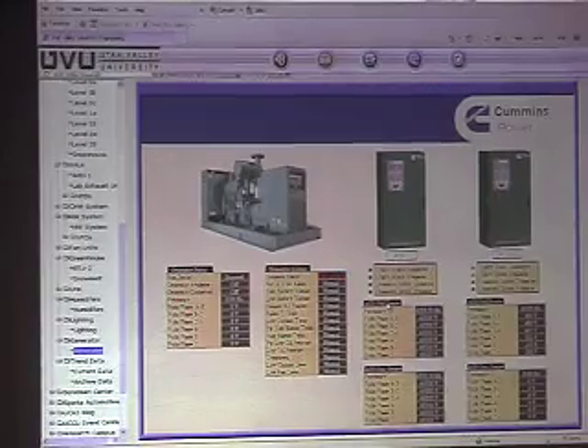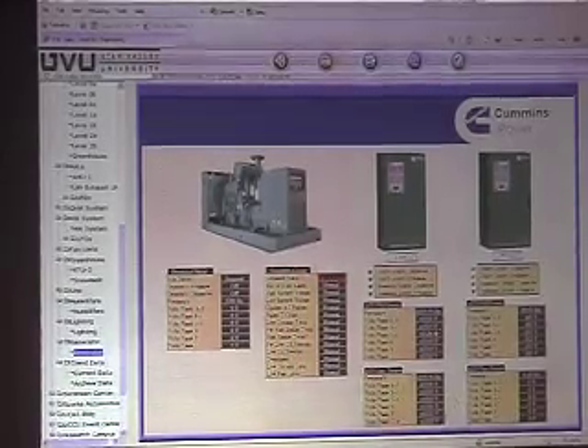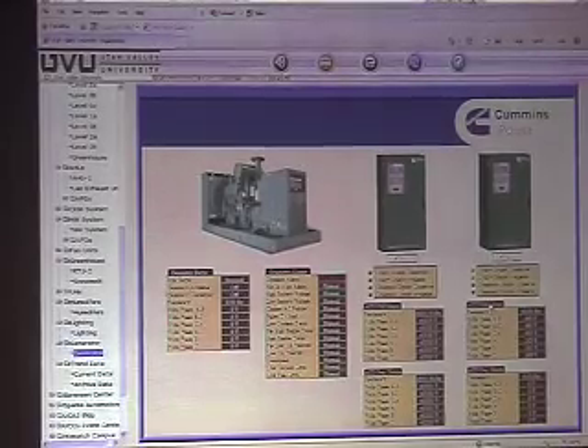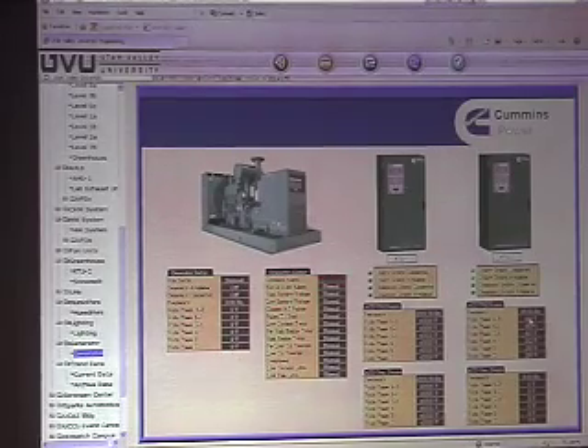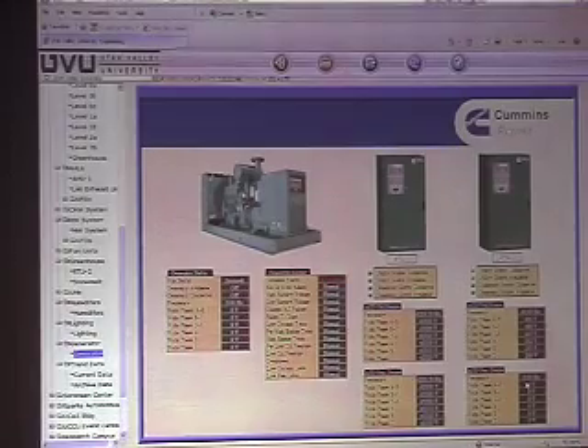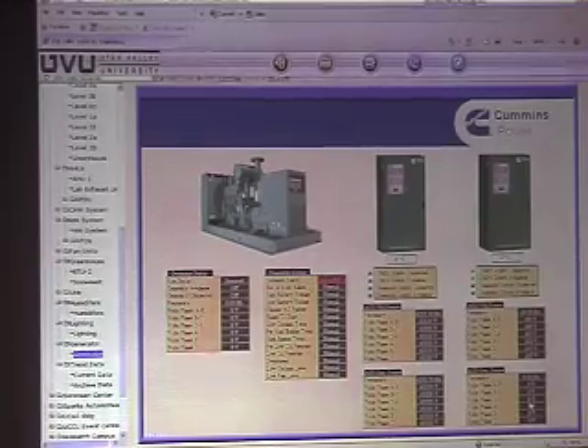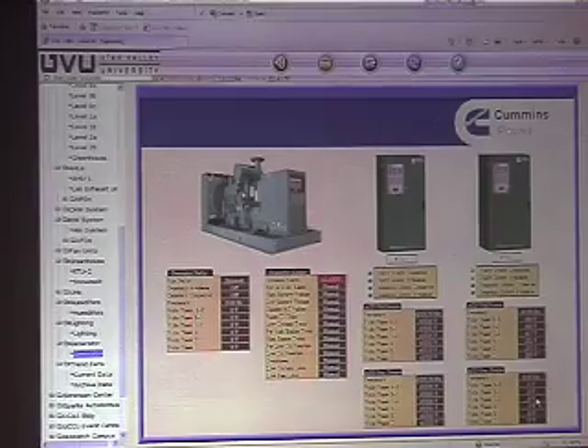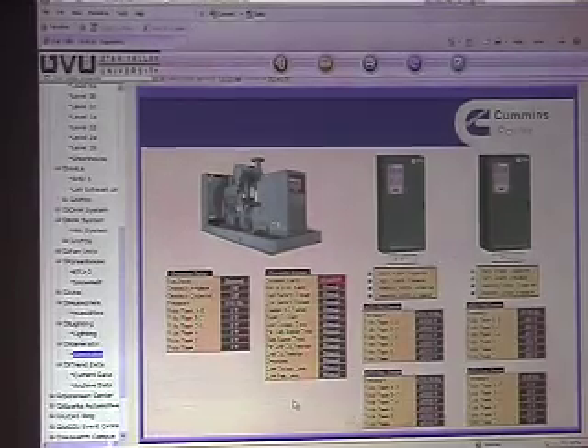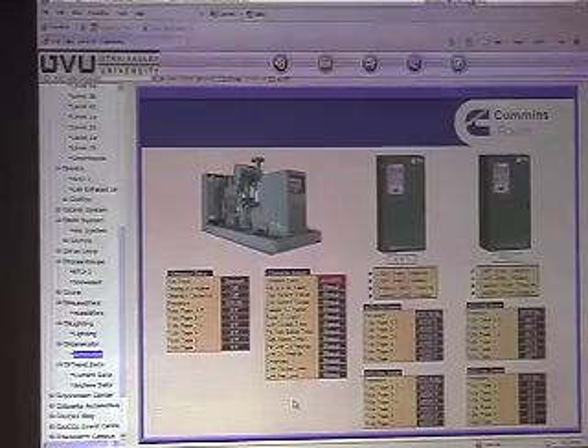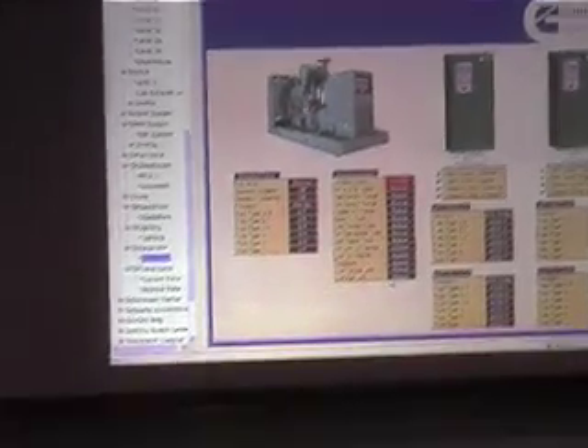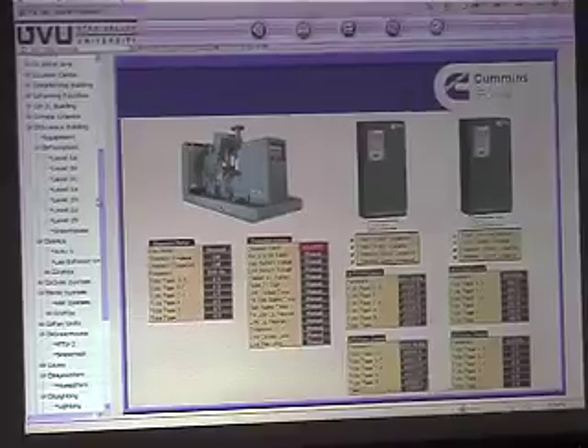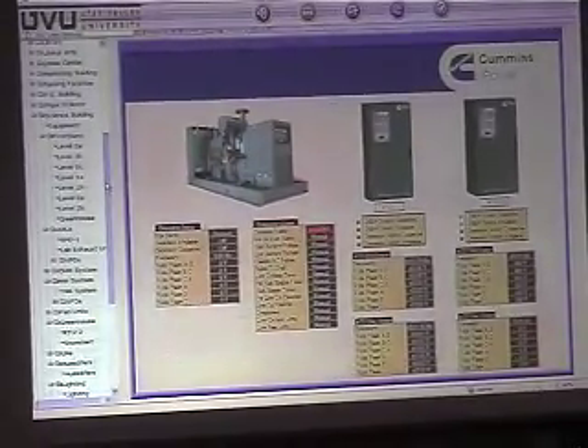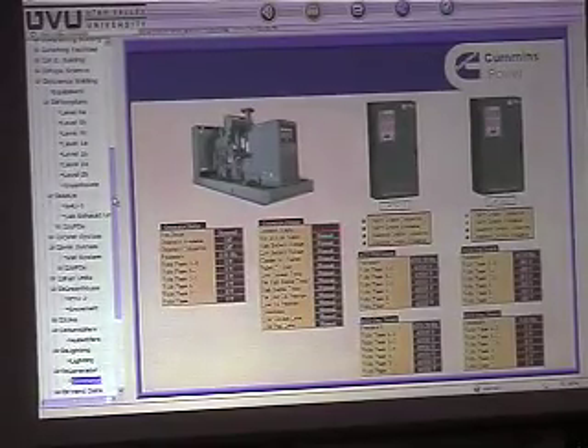And then your volts and frequency on your transfer switches. So you've got the utility source and generator source. When you lose power on your utility side, these will most likely go to 0. And then when your generator kicks on, you'll see voltage on this side here that is being supplied to the transfer switch. Where are the transfer switches located? They're right down here in the electrical vault, bottom floor. There's one that's for emergency, and there's one that's general. That's pretty much all the equipment in the building.